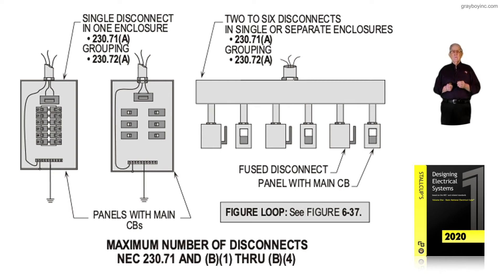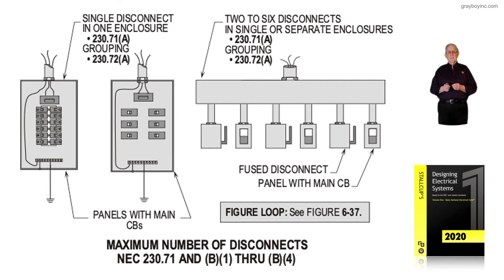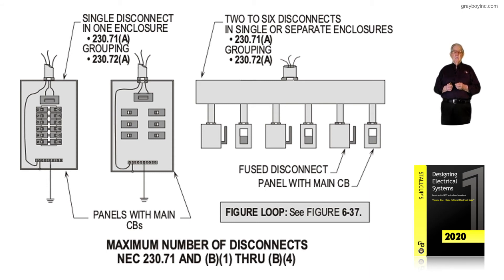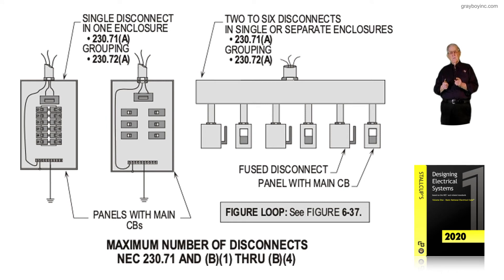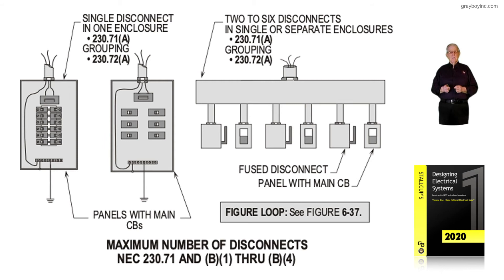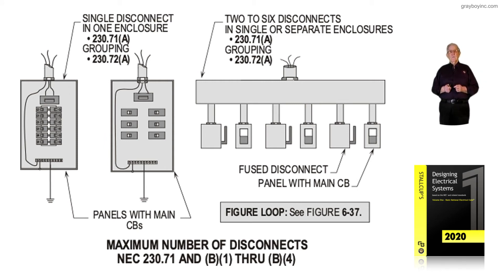We know that they have to be individual, as you see to the right of the illustration. Either one of those two on the left-hand side would have to have a main ahead of them. And in the illustration to the right, 230.72A, they have to be grouped as shown. We couldn't have, for example, a meter base outside with three mains and three more mains inside ungrouped — you'd have to have a main ahead of them, or two to six mains as shown to the right.